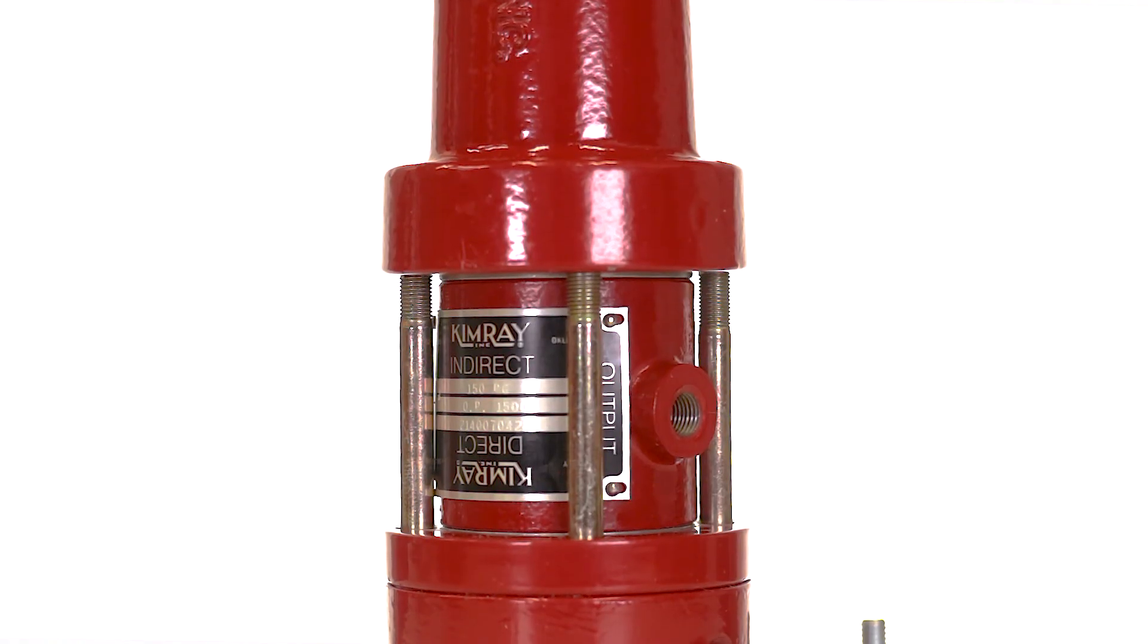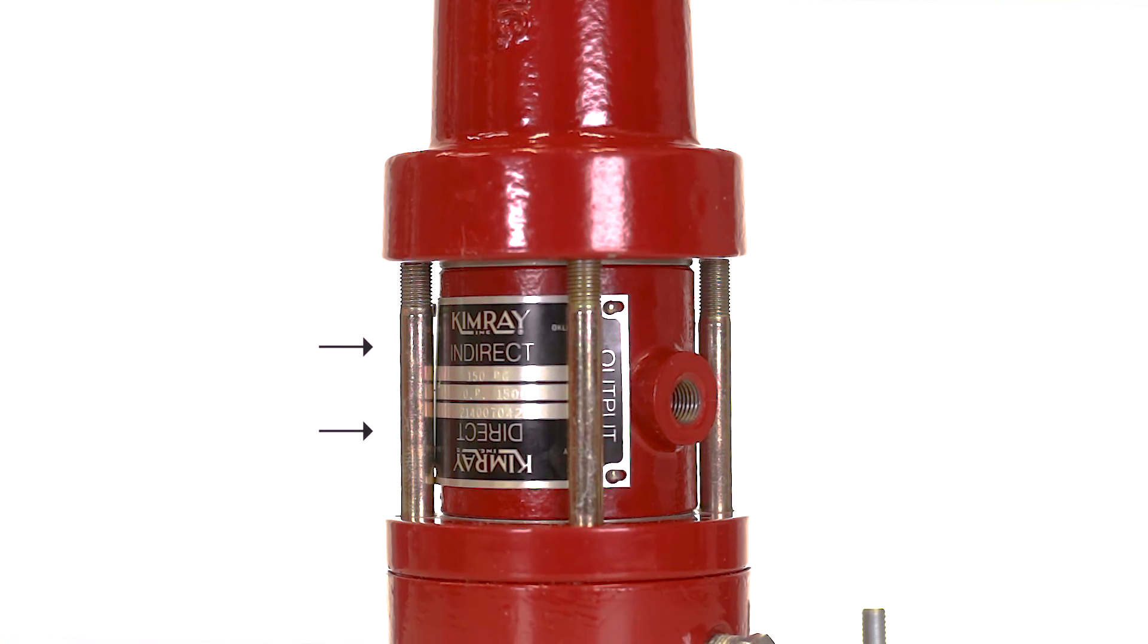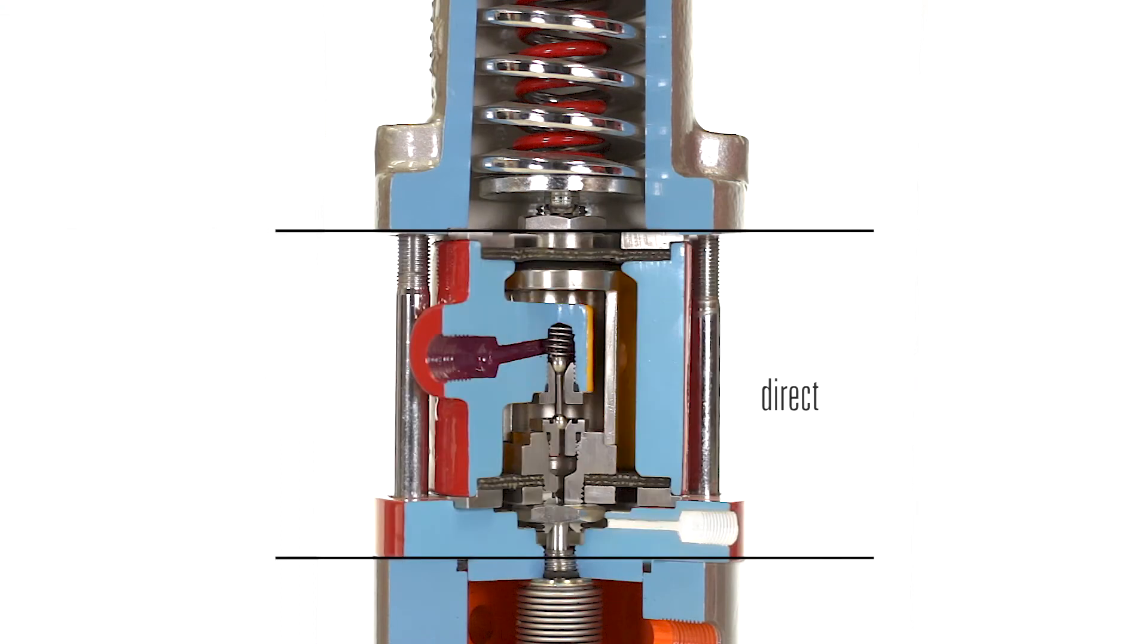The PG pilot is field reversible between direct and indirect operation and requires no additional parts. To switch modes, simply invert the middle housing.